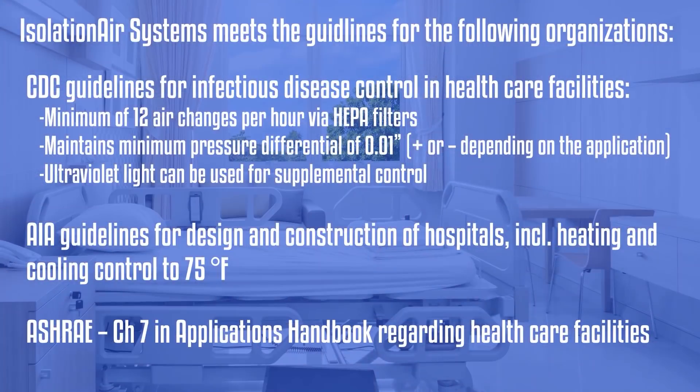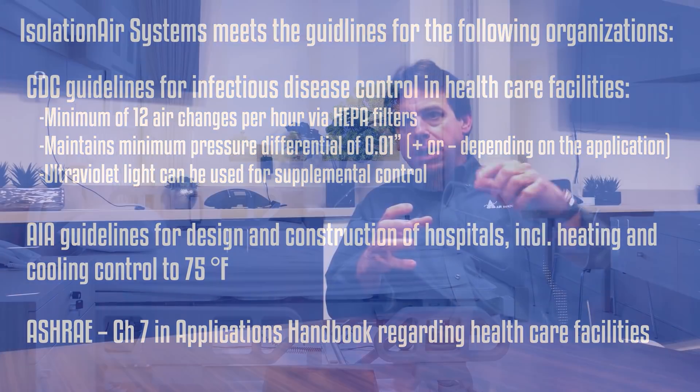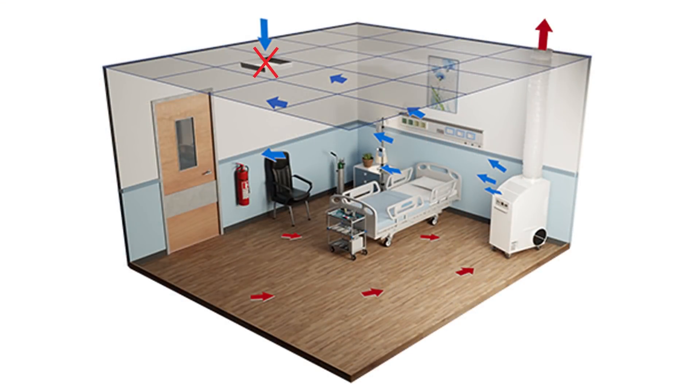To build a true isolation room that meets the CDC and AIA guidelines, it has to have a dedicated HVAC system and dedicated filtration system. It really is an isolated environment in the middle of a hospital. It doesn't share anything — it doesn't share controls, it doesn't share air. You can't have cross-contamination. You have pressure control: negative pressure or positive pressure control. As the name would tell you, it's an isolated space inside a hospital.